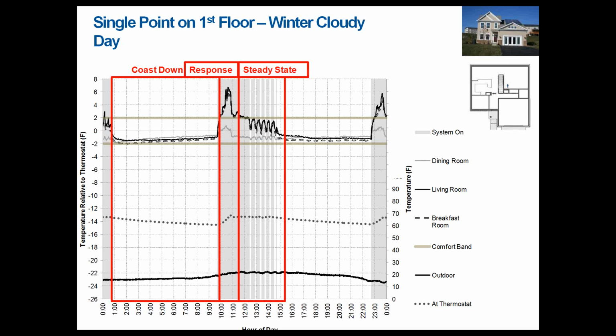Here is some data from that case. Let me explain this graphic a little bit. On the left side, we have the temperature in the zone relative to the thermostat. We've marked the comfort band we use, plus or minus 2 degrees Fahrenheit, shown as a gray band, and all of the rooms are plotted, sometimes staying within that band and sometimes going beyond it. This is the temperature of the room relative to the thermostat. For context, we've also included the outdoor temperature and the temperature at the thermostat. On this day, it was cloudy, and the temperature was around 20 degrees Fahrenheit.